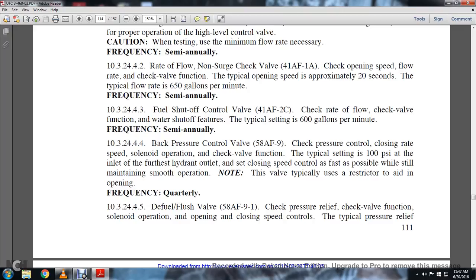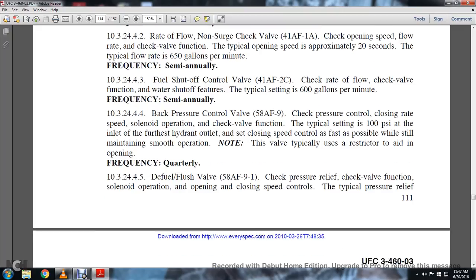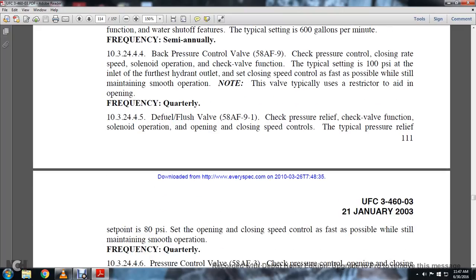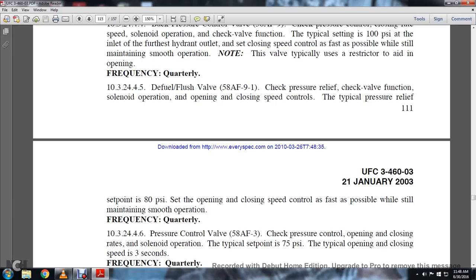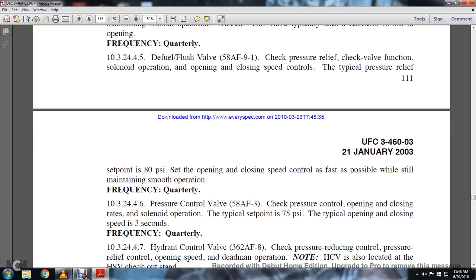The inspection is quarterly for back pressure control valves. The defuel flush valve: check the pressure relief, check valve function, solenoid operation, and opening and closing speed controls. The typical pressure relief set point is 80 psi. Set the opening and closing speed control as fast as possible, which still maintains smooth operation. The inspection is quarterly.